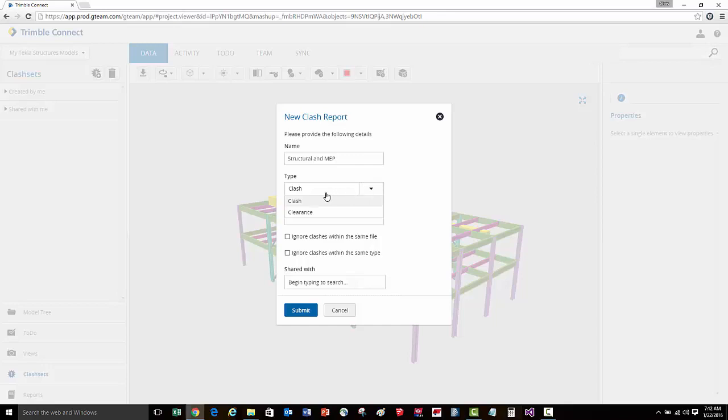We're going to specify the type of clashes to be clash only versus clearance. We'll set a tolerance here to be an eighth of an inch. We're going to ignore any clashes that are within the same file. We're only looking for clashes between the two different files.